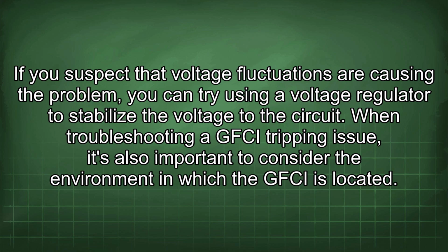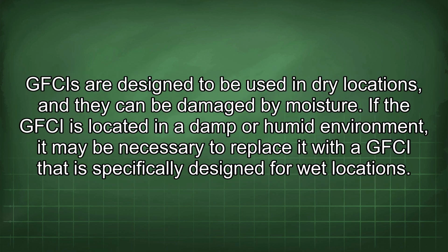voltage to the circuit. When troubleshooting a GFCI tripping issue, it's also important to consider the environment in which the GFCI is located. GFCIs are designed to be used in dry locations, and they can be damaged by moisture. If the GFCI is located in a damp or humid environment, it may be necessary to replace it with a GFCI that is specifically designed for wet locations.